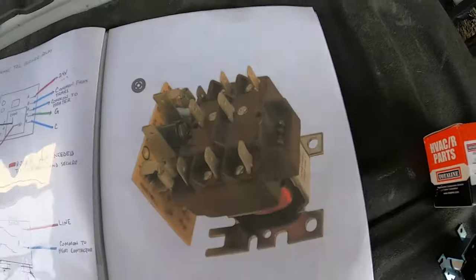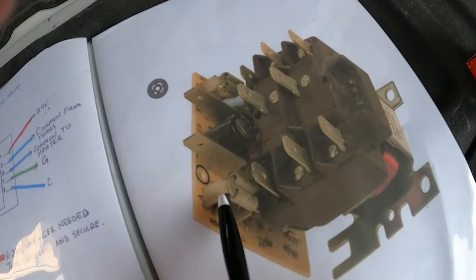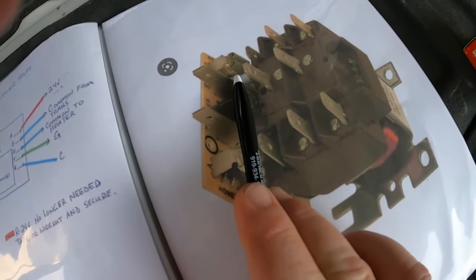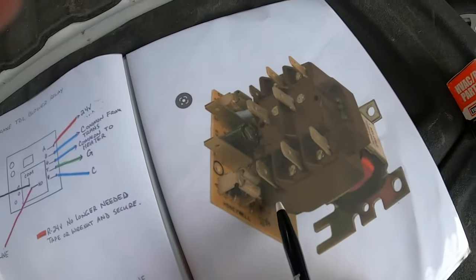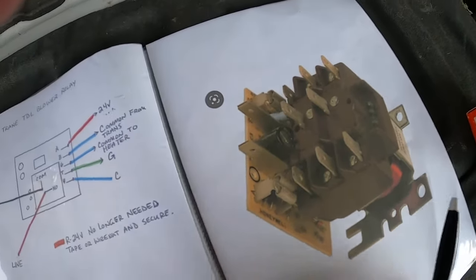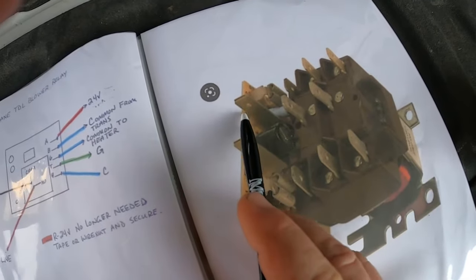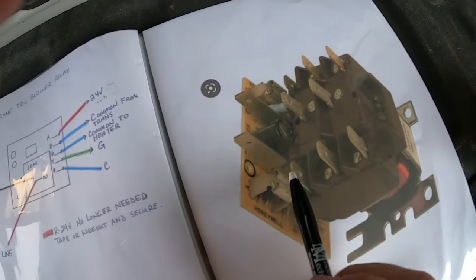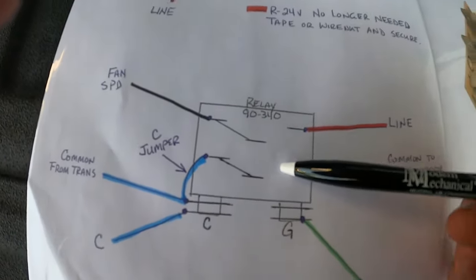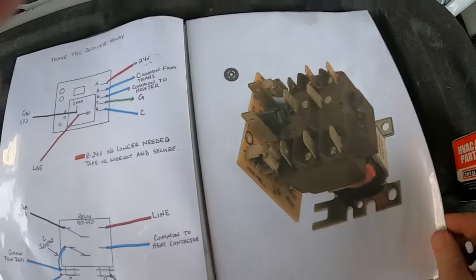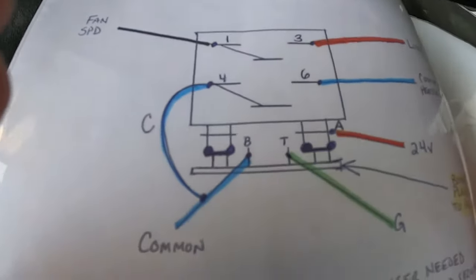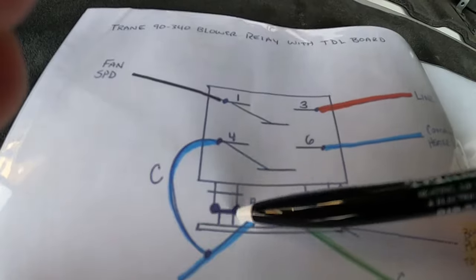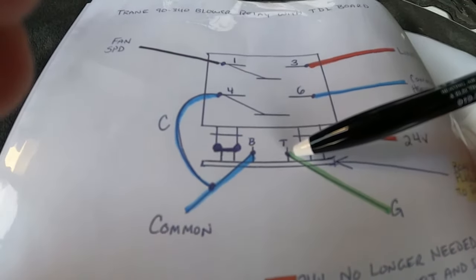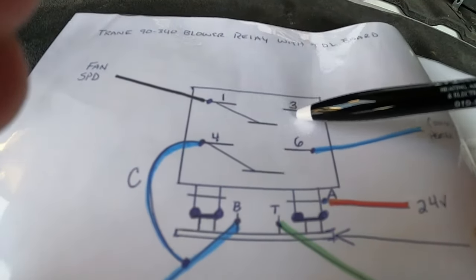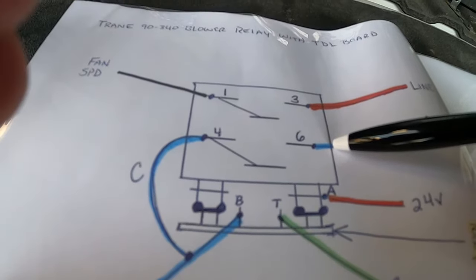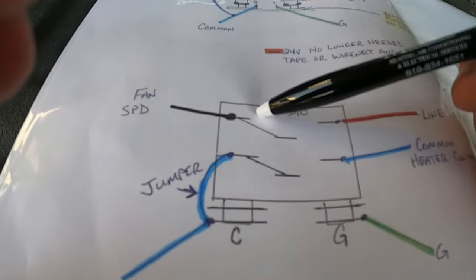The older version of that was this relay, and then it was plugged to this board here and here, and it had an R terminal that would power the timer in that. You would get your call for G in common, then it would initiate that timer. Then that relay was actually wired the same as it is wired here, and it would turn on your blower and it would turn on your heat strips. Here's that wiring diagram. There's your 24 volts that powers that board that's plugged to the bottom of this relay. You get your call for G, that relay closes, powers the motor, proves common to your contactor.